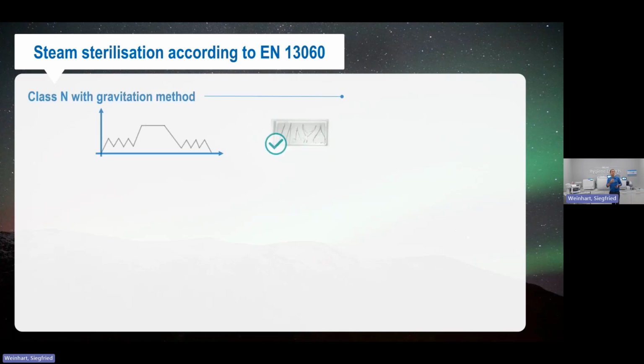One of the points this standard looks at is the classification of steriliser, and that's when we're talking about non-vac, S class or B class. Non-vacs are typically what we call downward displacement autoclaves. The way they work is there's no vacuum pump to pull any air out. Steam comes in through the top of the chamber and passively moves around inside that chamber, and by doing that it moves air around, but it's not particularly good at getting air out from in there.